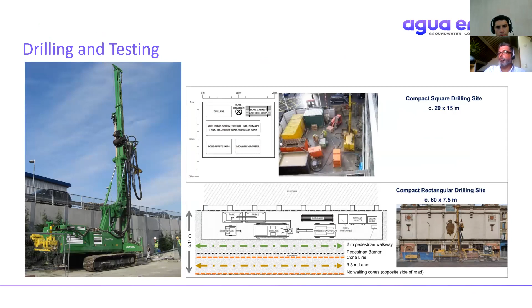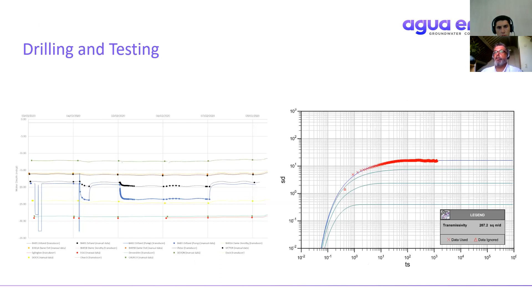Once we've drilled the wells, we test them with abstraction and recharge tests. Here's an example of the water level plots we get as pumps are switched on and off, showing levels rising and falling. This is often a regulatory requirement, but it also feeds into our design and pump selection, as well as the environmental impact assessment. Once the boreholes are drilled and tested, we can move on to detailed design.